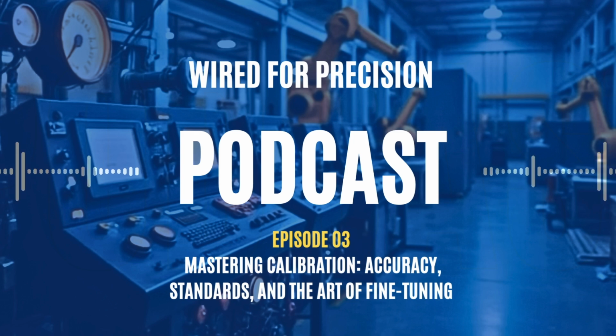This is one of the most debated questions in any quality or maintenance meeting. How often should we calibrate our instruments? The truth is, there's no universal answer. But here are the key factors that determine calibration frequency. First, instrument criticality. Instruments used in safety critical or regulatory compliant processes must be calibrated more frequently. For example, sensors involved in batch processing for pharmaceuticals may require monthly or even weekly checks.